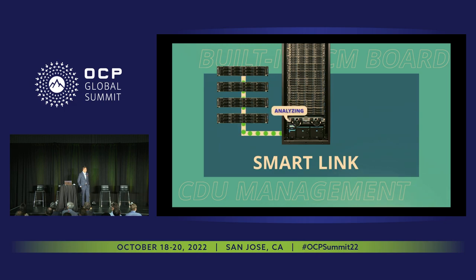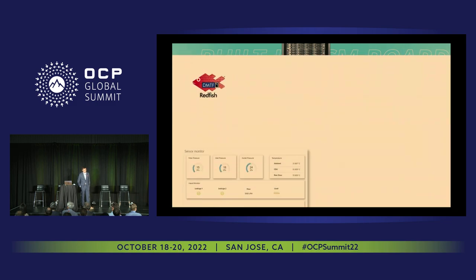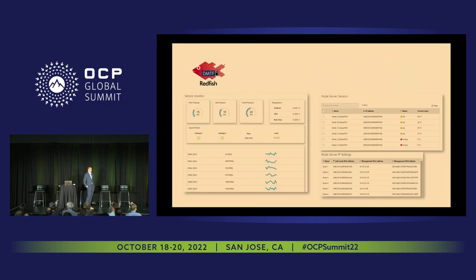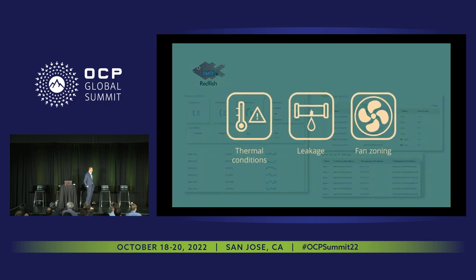Based on this smart link, the CDU uses this data to automatically analyze workloads and thermal data or status of the servers to then adjust CDU pump speed, fan speeds, and fan zones. A Redfish API web user interface is also used to monitor thermal conditions, leakage, and fan zoning for every node.